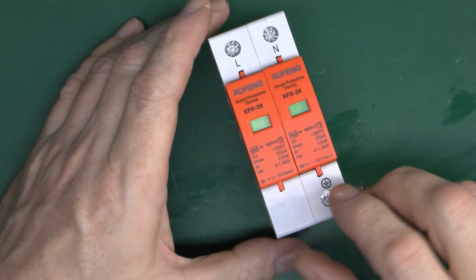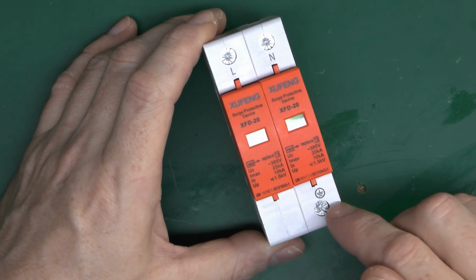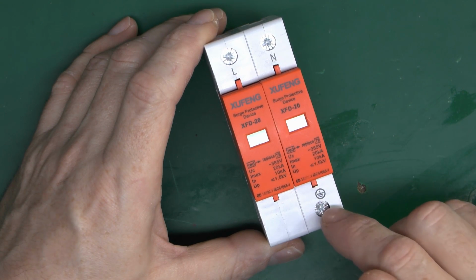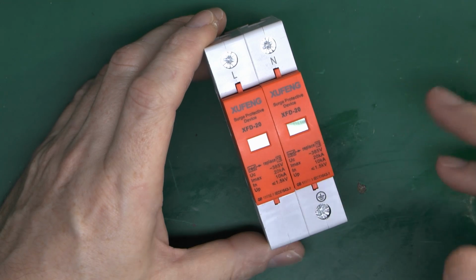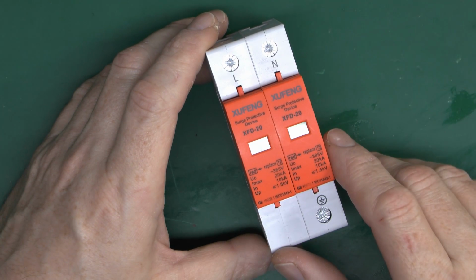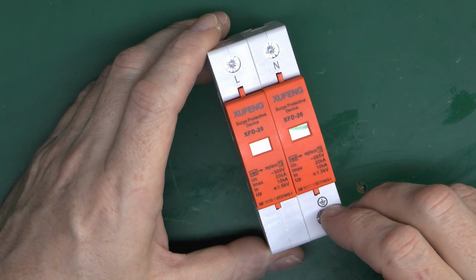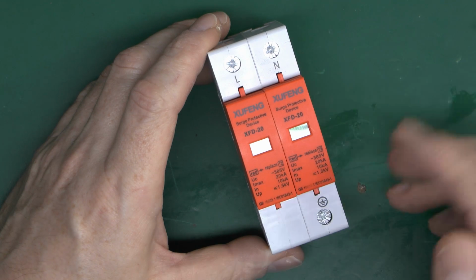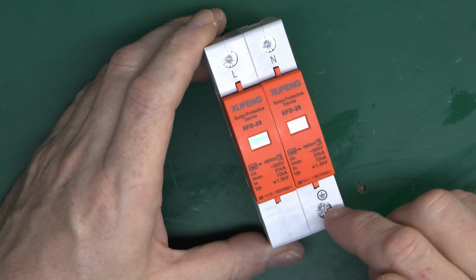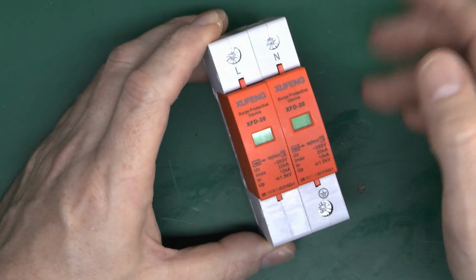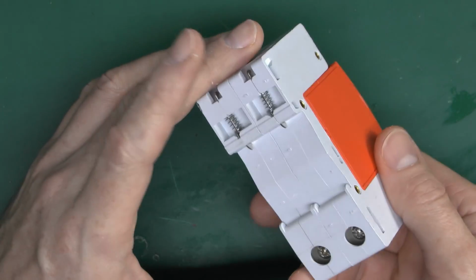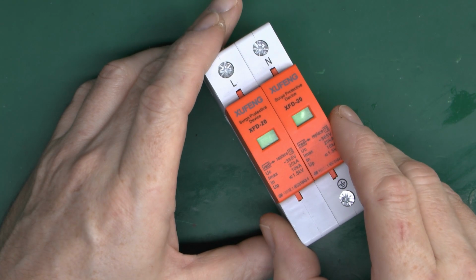But one thing that is important on these is the length of the wires that actually connect to the surge protective device, and this is in the wiring regulations, which we'll have a look at in a moment. But the length certainly is highly significant, and the idea is to have the length of the wires from the terminals as short as possible, and that's the distance between this thing and the rest of the installation.